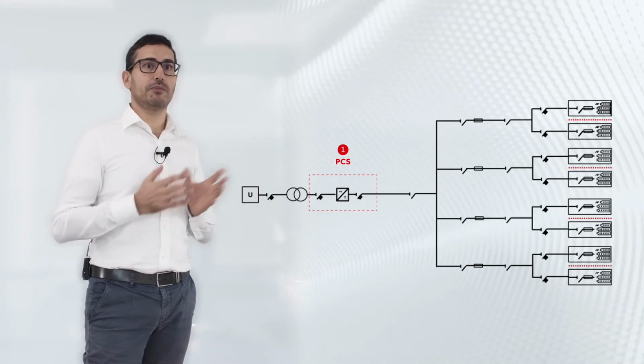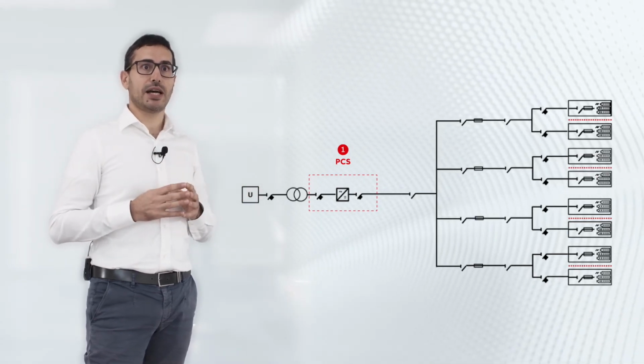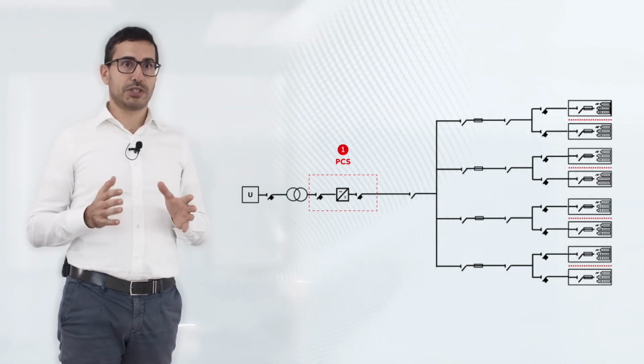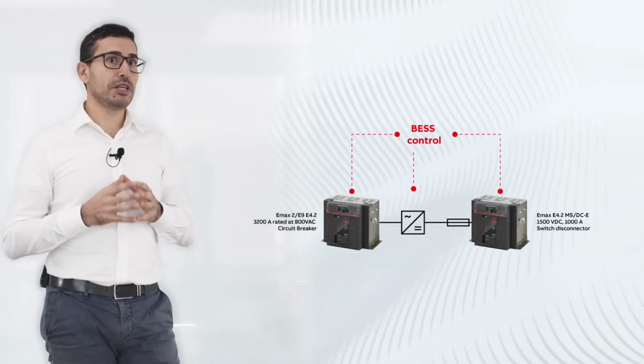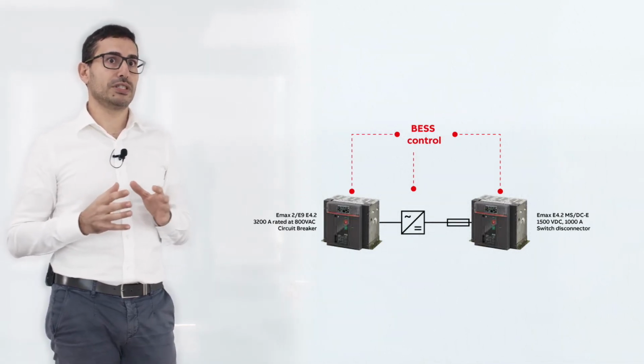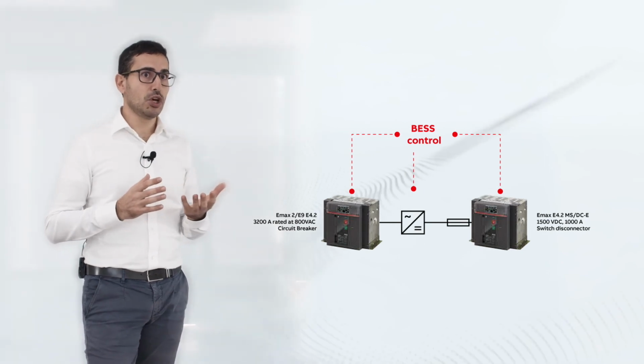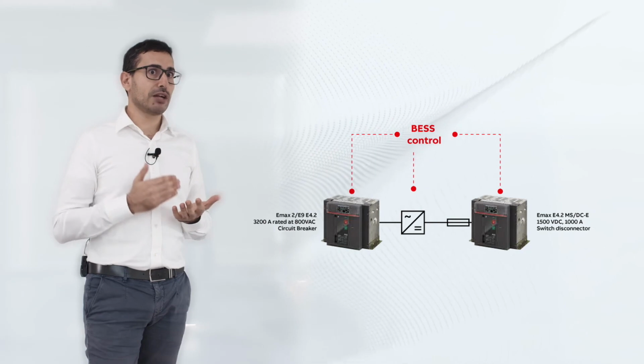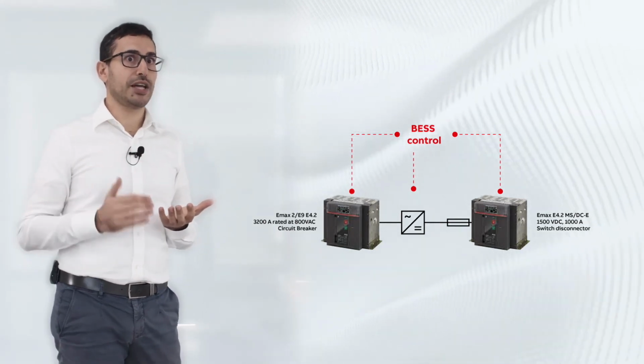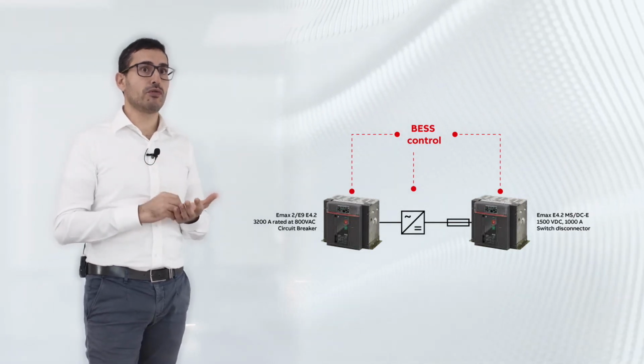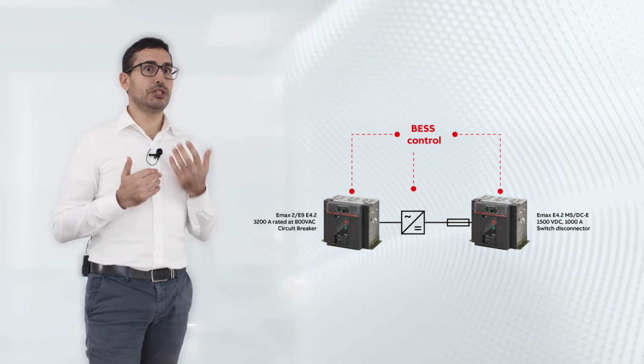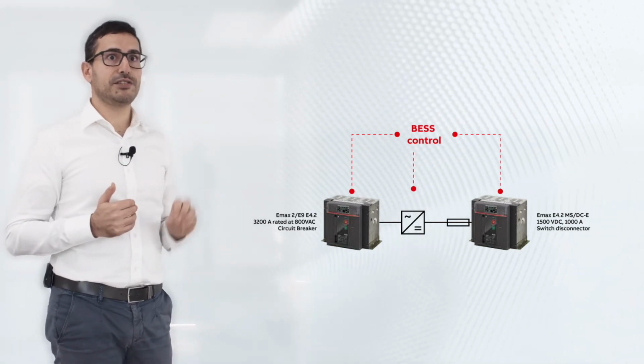On the AC side of the PCS, we do have an Emax E9 rated at 3200 amps. The Emax E9 provides a rated voltage up to 900 volts. That is extremely important value because it perfectly covers the 800 volt AC application, which is what we may expect for battery energy storage system which has distributed DC side at 1500 volt DC. But it also covers the plus 10% that most of the utilities require on the AC side of the PCS. E9 is another of the latest release on the market of ABB devices for energy storage application.